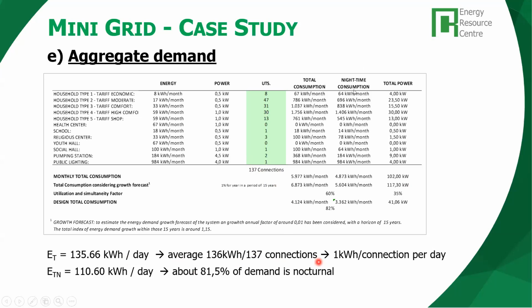So on average, we know that each connection has a different consumption. Of course, this is important when you do the contract for each type of customer, the type of demand that the customer has selected and will contract. But when we do the sizing, we can get from this example a reference of roughly 1 kilowatt hour for each connection per day. We have 137 connections and 136 kilowatt hour per day of demand. And we can see that more or less 81.5% of the demand is nocturnal. We can take a gross reference of 80% of the demand being nocturnal, okay?